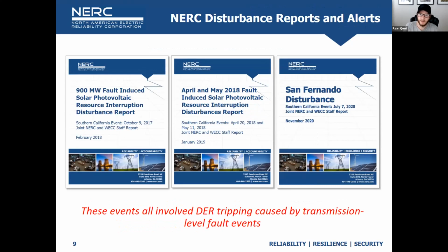So we've been studying really bulk system events where unexpectedly, particularly in California, we've seen a lot of solar PV resources trip offline when we have a bulk system fault. And this goes all the way back to the notorious Blue Cut fire, where we spun up a NERC group, and that really initiated a lot of the NERC work on inverters and in a lot of ways the changing resource mix, particularly around the changing technologies associated with that resource mix. And so more recently, well, not even that recently, but October 2017 up until fairly recently, we've seen a number of events where DERs are being identified as being involved in these events.